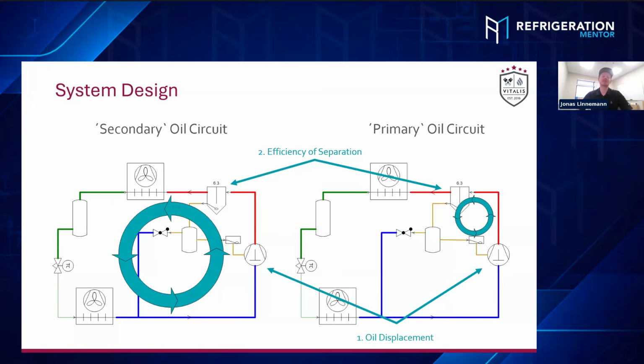Yeah. And as long as you don't have a leak, but you miss some amount of oil after a while, there's a reason for that, right? If you're just refilling the oil without considering any measurements, at some point it will come back and potentially destroy compressors or reduce the efficiency in the evaporators. If you just trap all the oil in the evaporators, obviously the oil is not a good heat transfer fluid, and it's not evaporating. It's not making it cold. So you want to have the CO2 inside, not the oil. And that all affects the system's efficiency and especially the reliability of the system.